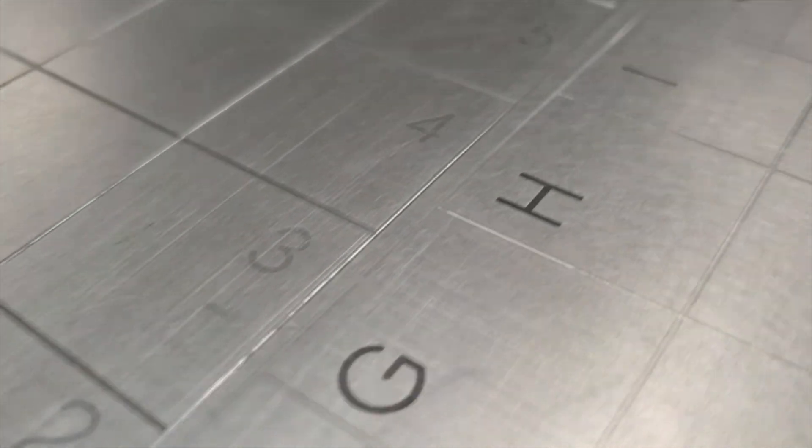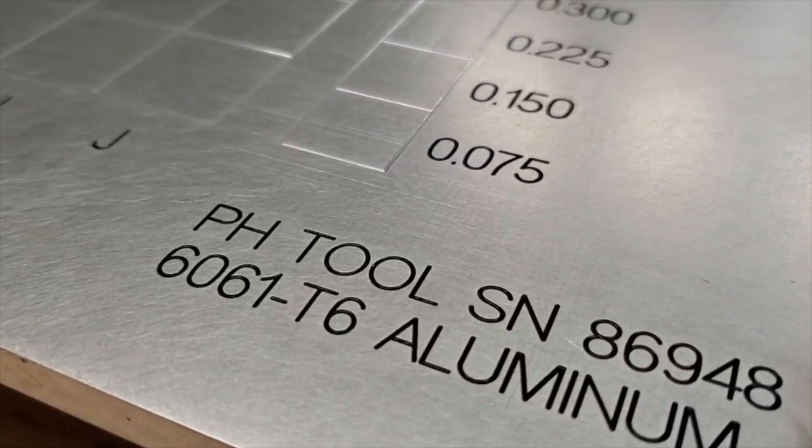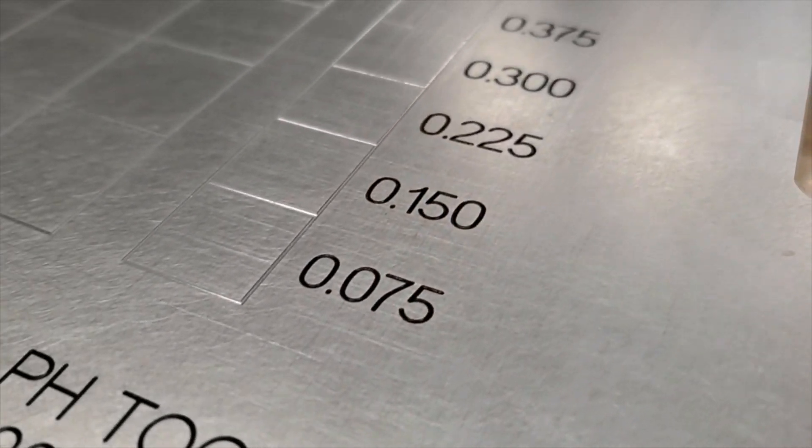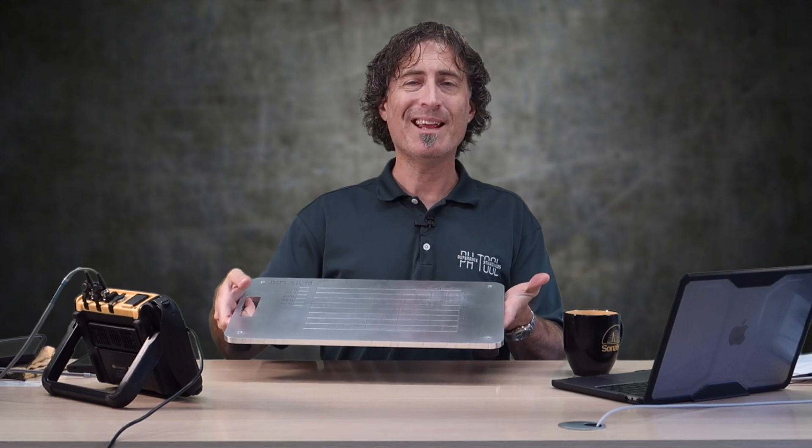The plate has a number of features designed into it. On the top side we've got a grid machined in, and the lettering on the horizontal and vertical axes are paint-filled so you can see them better. There's a built-in step wedge on the right-hand side. This plate is made out of aluminum and it's three-eighths of an inch thick, so the step wedge goes from 0.075 to 0.375. You can get these in other materials like steel, but being aluminum it's nice and light for training and there's less risk of hurting yourself if you drop it on your foot.